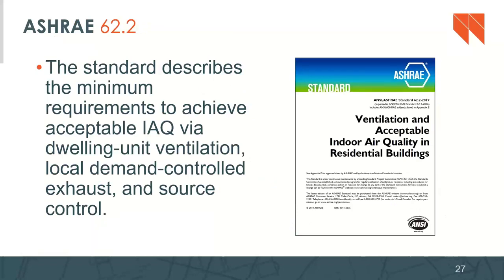So what guides us as designers in terms of how to do this? ASHRAE 62.2 is the one for dwelling units and homes. ASHRAE 62.1 governs more of the commercial side of things, so offices, schools, laboratories. But 62.2 is what we use to achieve acceptable indoor air quality via dwelling unit ventilation or whole house ventilation. It includes local demand controlled exhaust and source control. And it also includes that whole unit ventilation. So we'll talk more about that in a second.